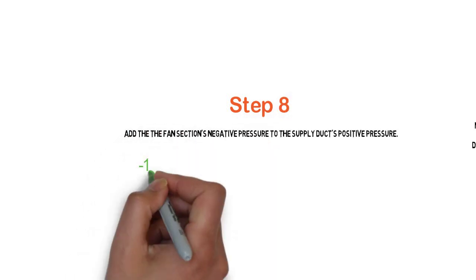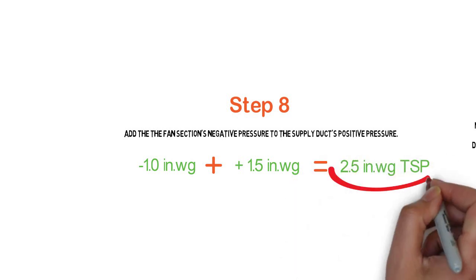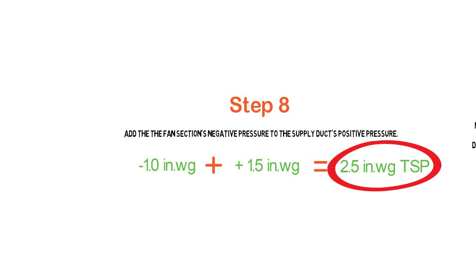Now we're going to add them together. Even though the return was a negative number, we're going to treat it like a whole. So 1 inch plus 1.5 inches equals 2.5 inches total static pressure, or TSP.